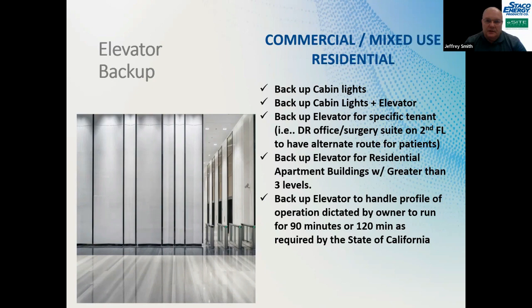Like anything, 90 minutes is what they were originally looking at for UL 924, but because this is something different, nobody really knew what to do. So they said they want to use UL 924 units, but in California want 2 hours. In New York and New Jersey, they've been saying 15 to 20 minutes, with a generator, or they just basically want to make sure people get down to the first floor, the doors open, and it stops. So these are the different options available.